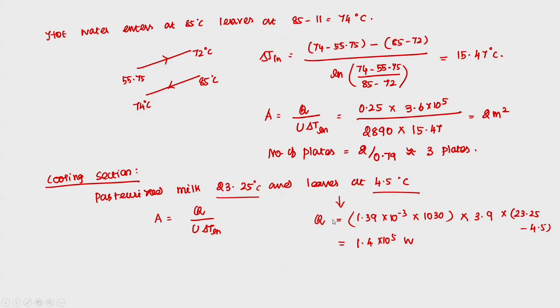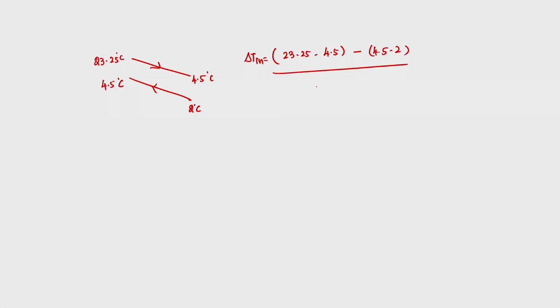So, we know Q, then we are supposed to calculate the logarithmic mean temperature difference. In the cooling section, the pasteurized milk enters at 23.25, which is cooled to 4.5. In the same way, my cooling water enters at 2 degree centigrade and leaves at 4.5 degree centigrade. So, del T ln is 23.25 minus 4.5 minus 4.5 minus 2, over ln of 23.25 minus 4.5 divided by 4.5 minus 2. So, the logarithmic mean temperature is coming around 8.06 degrees centigrade.